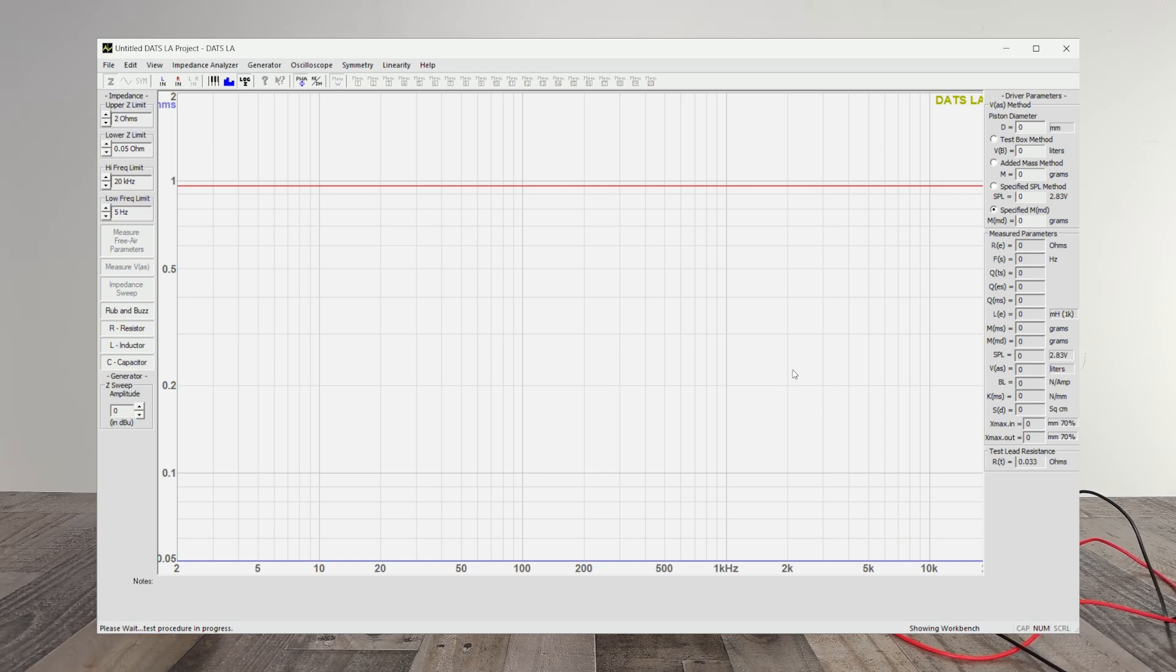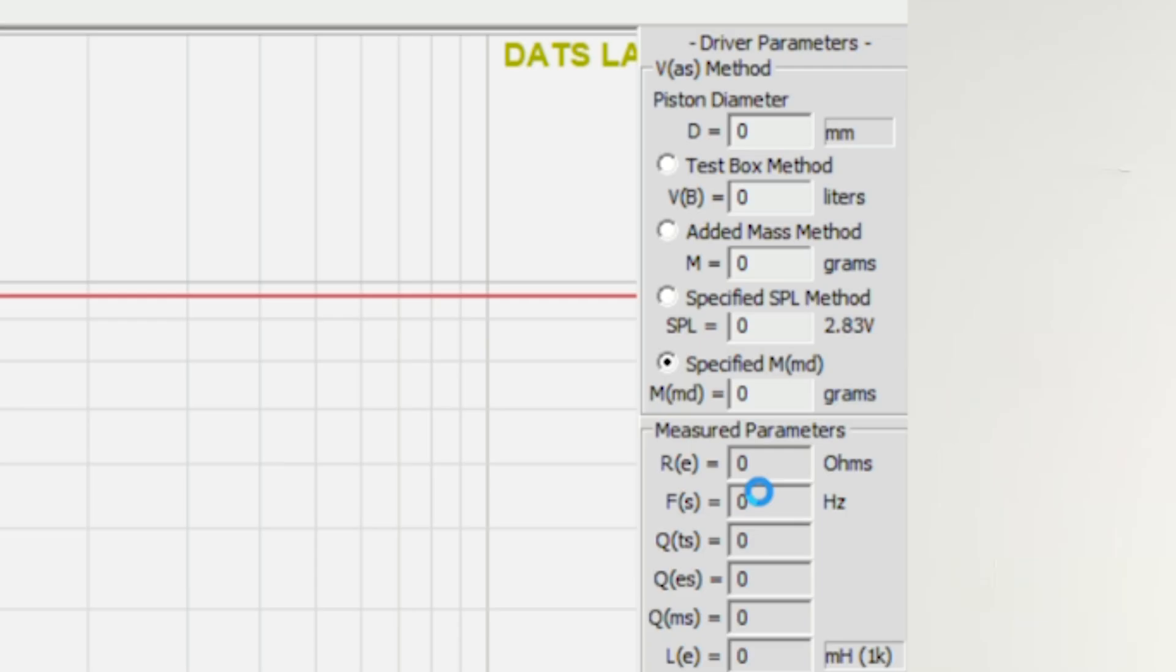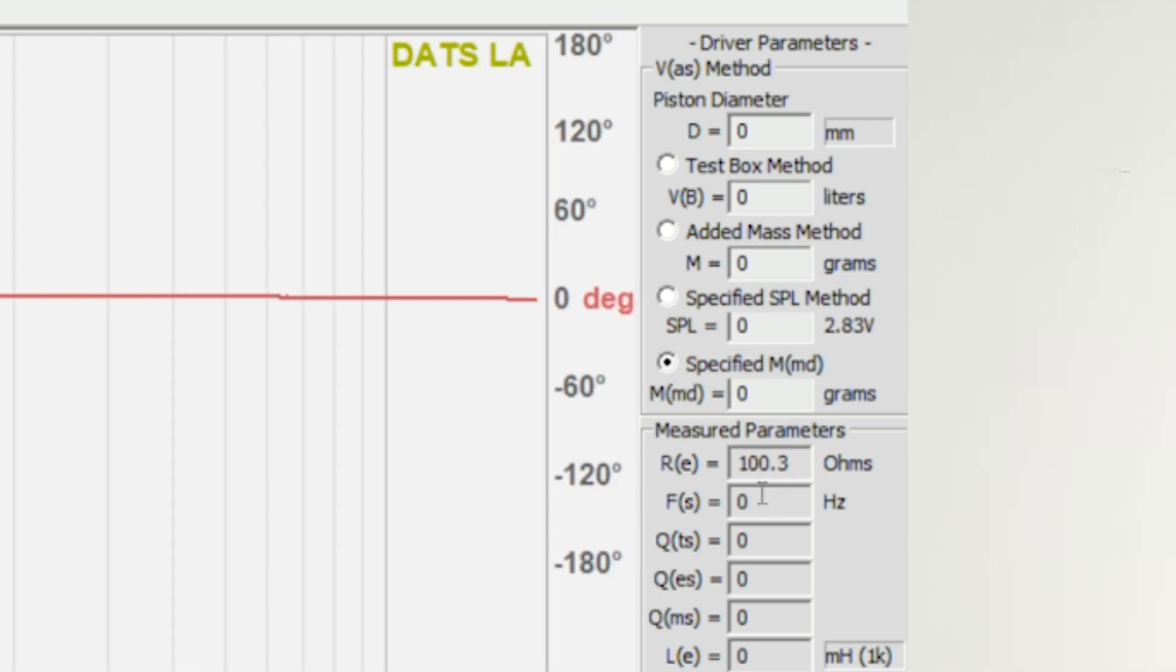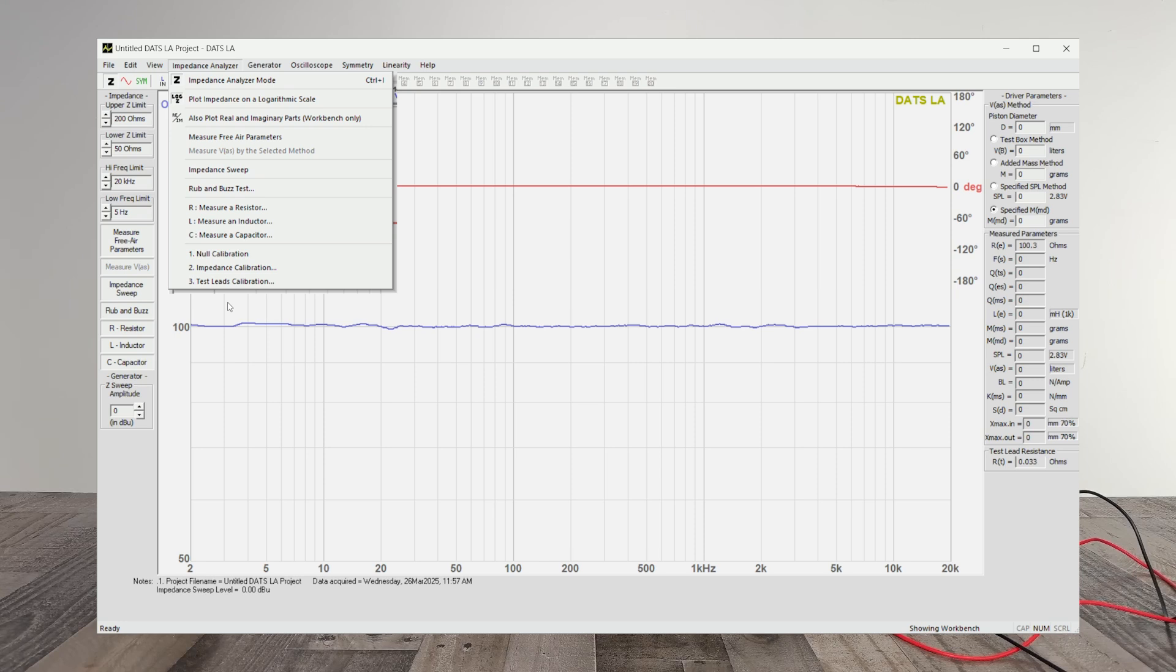So we hit OK, and now it's calibrating it. And up here in the RE section, it will let you know what it calibrated that 100 ohm resistor. This is a 100.3. That's well within the plus or minus in the calibration.